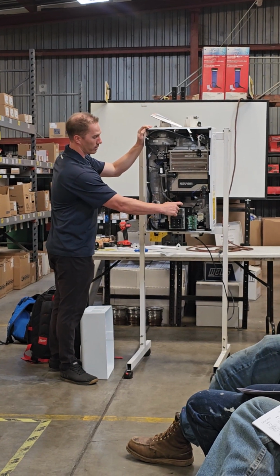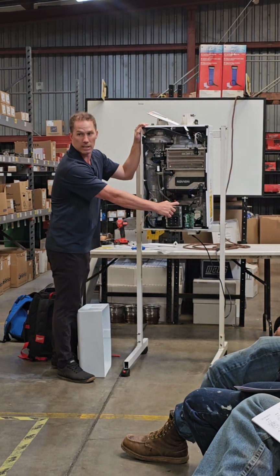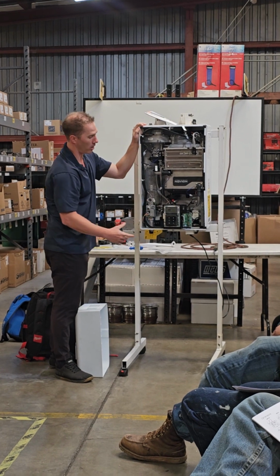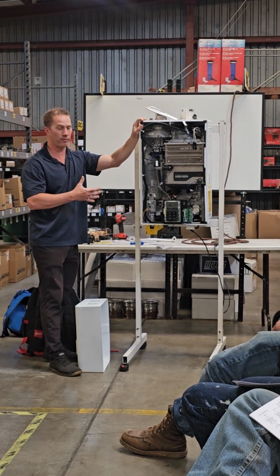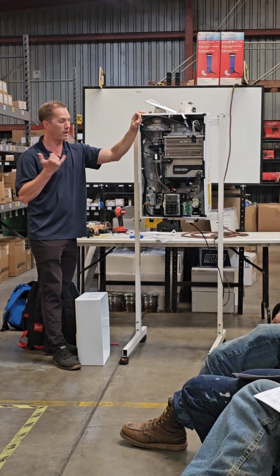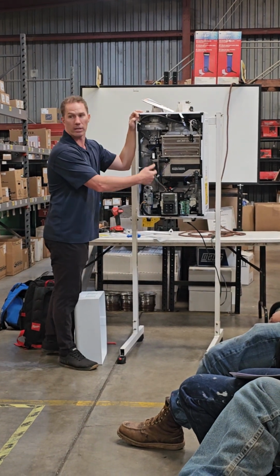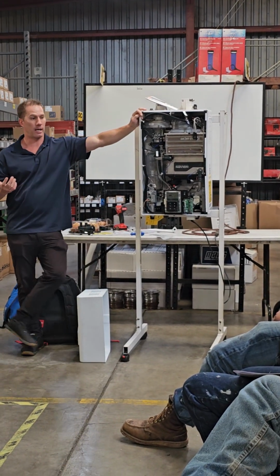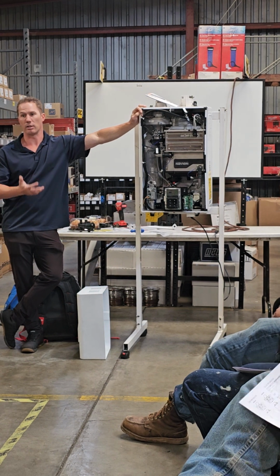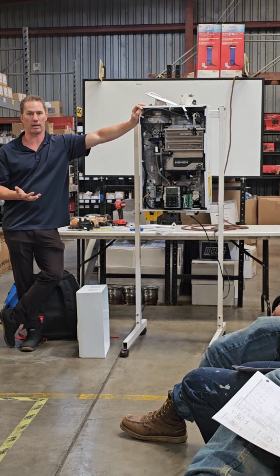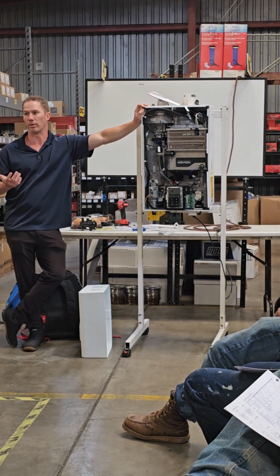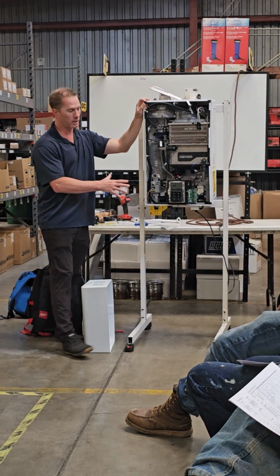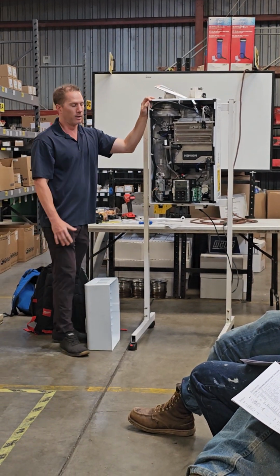With the older unit, there was a little flap up here with 10 dip switches on top, and depending on the configuration—well, recirc, this or that—you had to flip all the different dip switches. 90% of the time, people didn't set them right, so Navien decided to get rid of the dip switches. Now it's all handled in the Start Wizard.